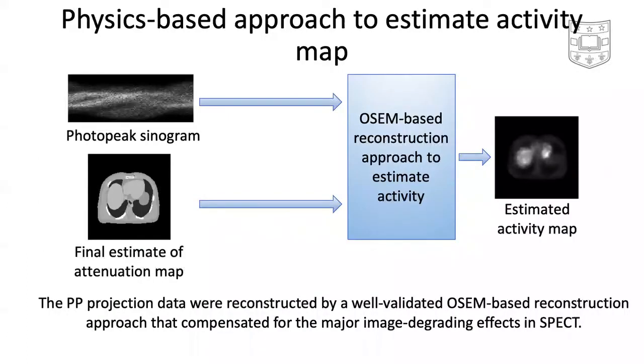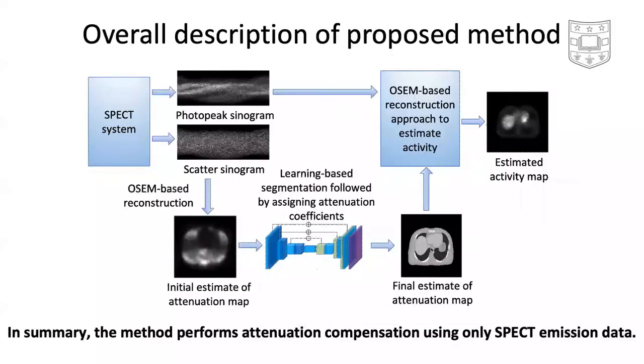Next, the photopeak sinogram data and this final estimate of the attenuation map are input to an OSEM-based reconstruction approach to estimate the activity map. This approach compensates for attenuation using the provided attenuation map. Additionally, this method also compensates for scatter, collimator-detector response, and noise. In summary, the method performs attenuation compensation using only SPECT emission data and without requiring any separate transmission scans.